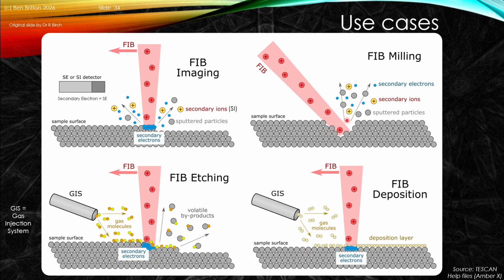In this case, we have these sputtered particles. As they get ejected from the FIB space, they get perhaps put behind the beam, and it's kind of like digging a hole on a beach. The sand can pile up next to the hole. It can make it difficult to dig deeper into the beach itself. Well, if you attach a volatile byproduct to the side of it, you can enable those things to effectively float off and not adhere back to the surface. And that's what the FIB-enhanced etching approaches enable us to do.